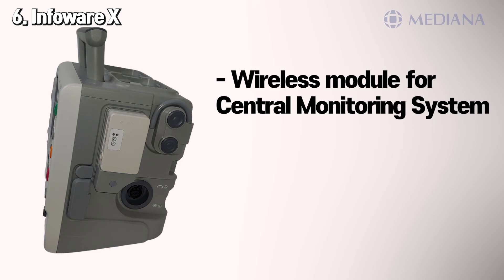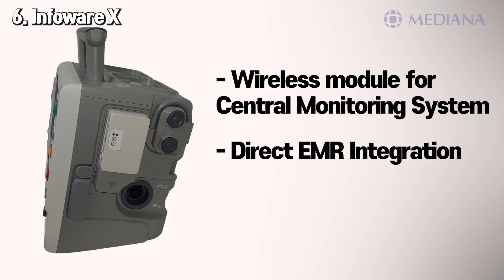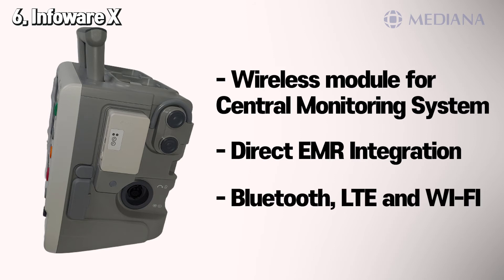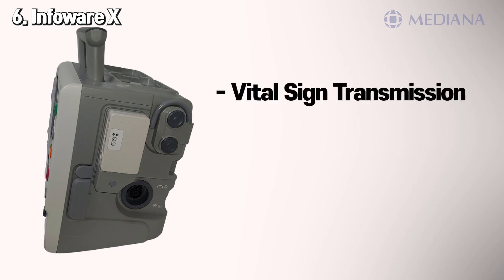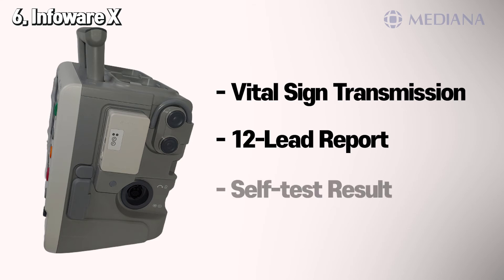Infoware X is Mediana's wireless module for a centralized monitoring system. It supports direct EMR integration without a CMS using a variety of protocols including Bluetooth, LTE, and Wi-Fi. All vital signs are transmitted to medical staff in the hospital. 12-lead ECG reports of 10 seconds are also transmitted to medical staff, and self-test results and log files are transmitted to the biomedical engineer.